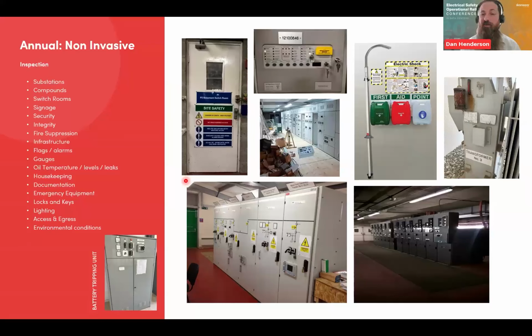So things like that. And I've seen mechanical systems included where you've got a valve. Some people will close the valve but leave the panel enabled because they've got a mechanical isolation there. In the event of it operating, it would discharge the bottles up to the valve, and then pressure relief via a pressure relief valve into atmosphere. So you'd lose any of your fire suppression. So it's so important, especially from a loss prevention and risk management perspective, that if you have got that in place, people understand how to use it.